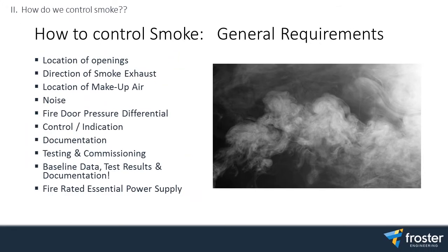General requirements. So location of openings, direction of smoke spill. Obviously, we have to provide separation between any smoke exhaust path and an intake path. We're not short-circuiting. So again, that's a planning issue with the architect, with surveying. We might have a good strategy early on that allows us to set it up very easily from the beginning.